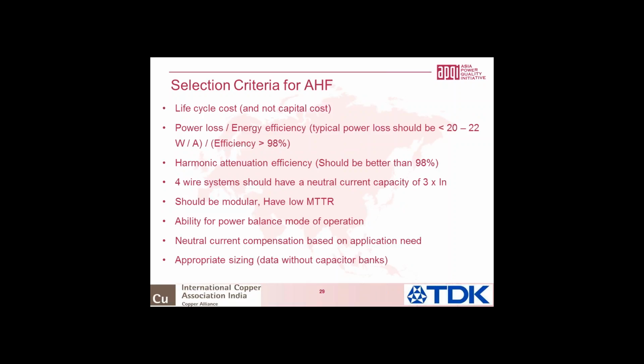One of the key issues for active filter is, though it generates reactive power and cancels harmonics, it consumes a lot of real power. If you see, some of these active filters can have an efficiency as low as 95, 96, or 97%.